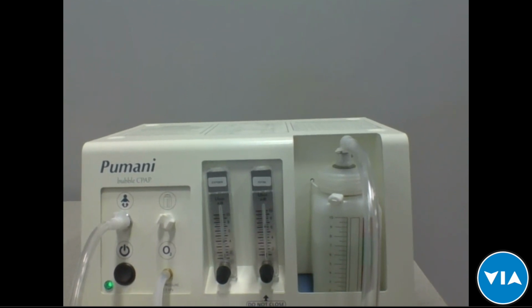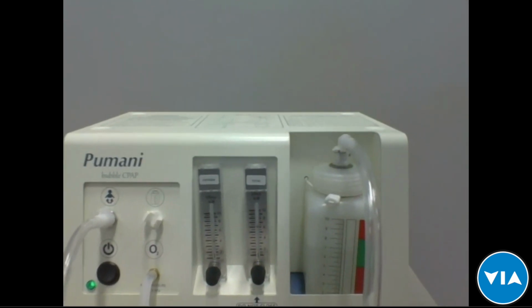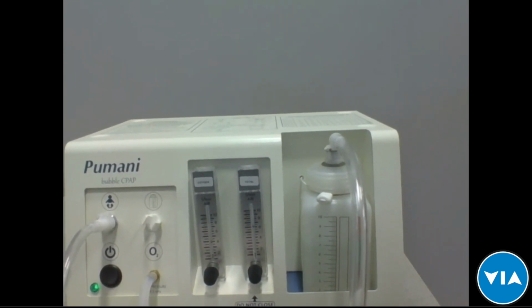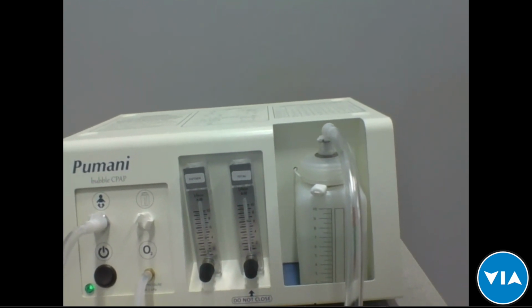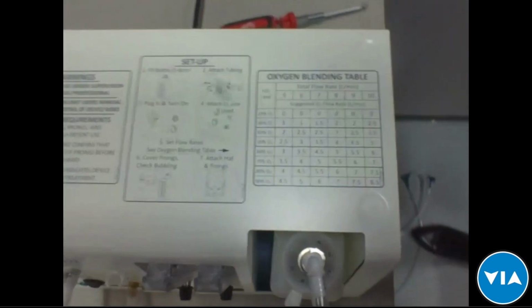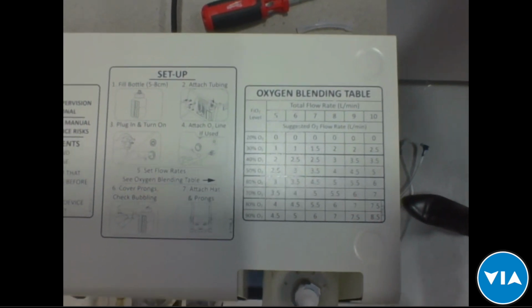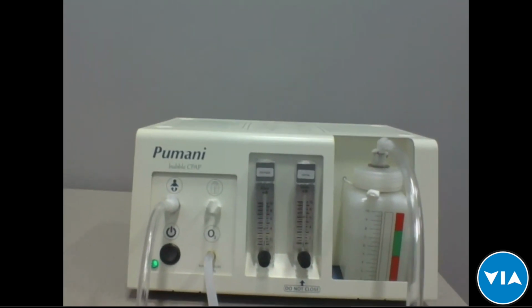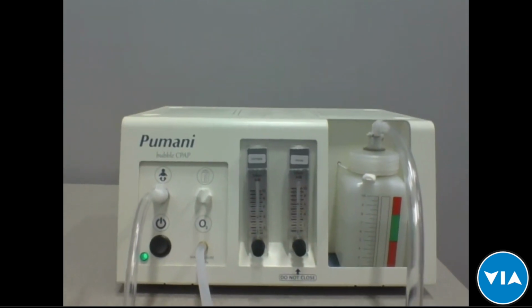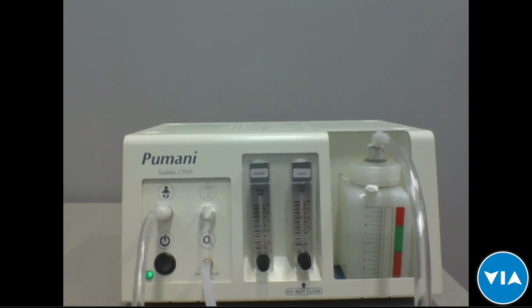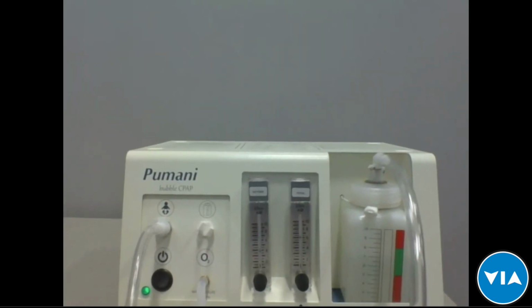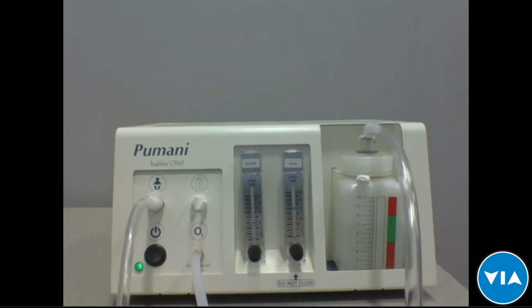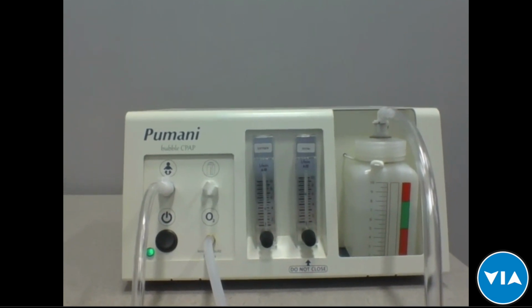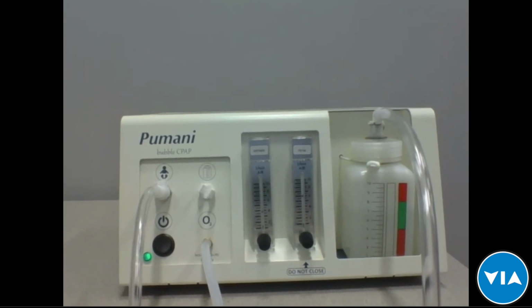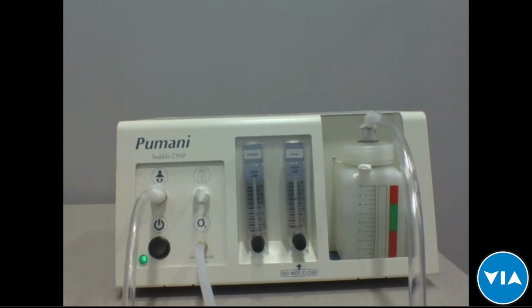And 50% of that, so 3 liters per minute, is oxygen, and 6 liters per minute total. So then there's 3 liters per minute of room air. So it's blended, and that puts us, I think, at about 60%. I'd have to look at the table. Let's see what that is. Yes, approximately 60% FiO2. The FiO2 depends, obviously, on the baby's condition, their oxygen saturation levels according to a pulse oximeter, and of course the clinical signs. And that's according to you as clinicians, how much FiO2 you want to give them. You have options from 21%, which is room air, all the way up to almost 100% oxygen with the Pumani.